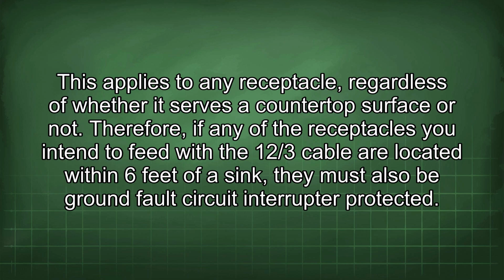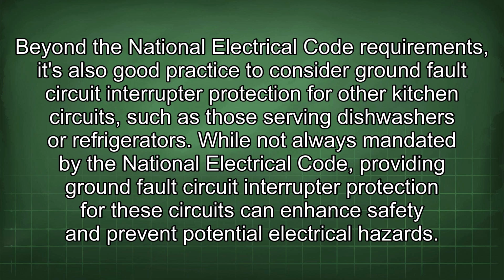Therefore, if any of the receptacles you intend to feed with the 12/3 cable are located within 6 feet of a sink, they must also be ground fault circuit interrupter protected. Beyond the National Electrical Code requirements, it's also good practice to consider ground fault circuit interrupter protection for other kitchen circuits, such as those serving dishwashers or refrigerators. While not always mandated by the National Electrical Code, providing ground fault circuit interrupter protection for these circuits can enhance safety and prevent potential electrical hazards.